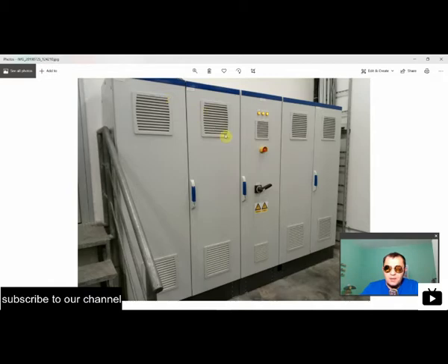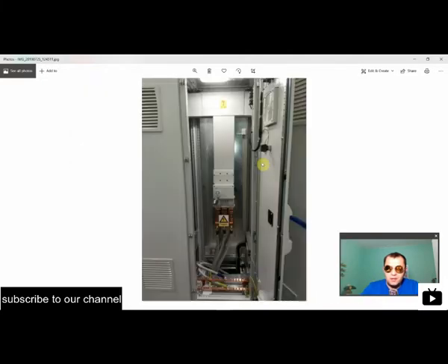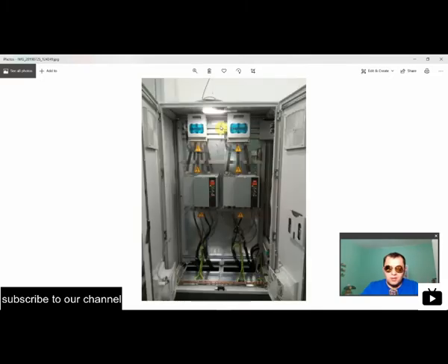But as I said, it wasn't an issue because the current is split at this point, and only the main busbar, the infeed busbars, had to be a little bit thicker, so 50 times 10 millimeters. So the first thing I had to do is to dimension the power distribution system. To do that, I used software called Simaris Design. I'm going to talk about this software in the next video.